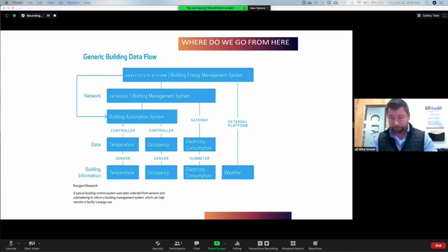But the unification, we generally find this in a couple different divisions of the specification, which is Division 25 and 26. So data collection is the predominant force moving the benchmark. All the BMS systems are derived to produce data that will better allocate resources for the facility. Whether it be BACnet, LonWorks, or Modbus, data is the future.